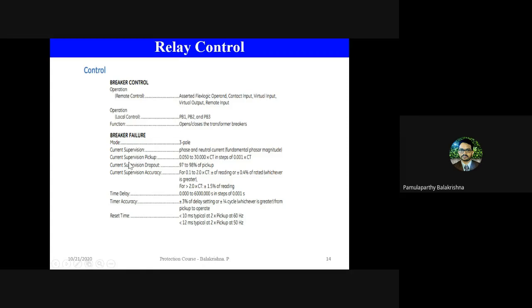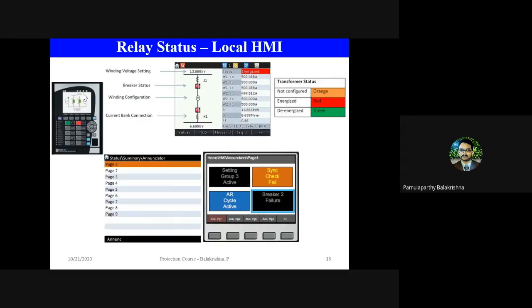If it doesn't operate, the relay will wait for some time, which is again configurable, and then it will immediately send the signal to the upstream breaker so that it will clear the fault. So a relay can not only send a communication signal to the local breaker, but it can also send one to the upstream breaker when it sees a breaker failure.